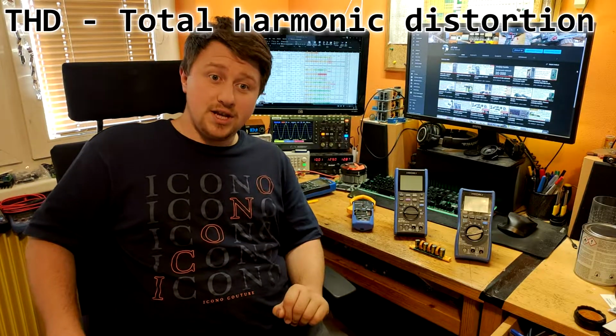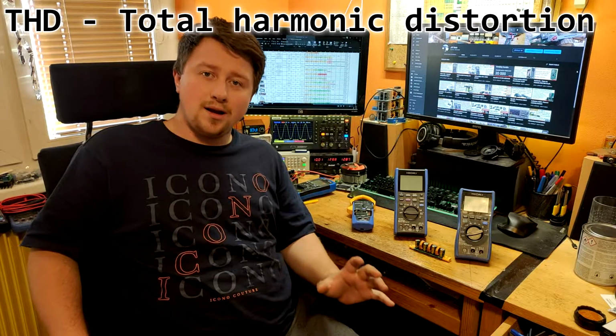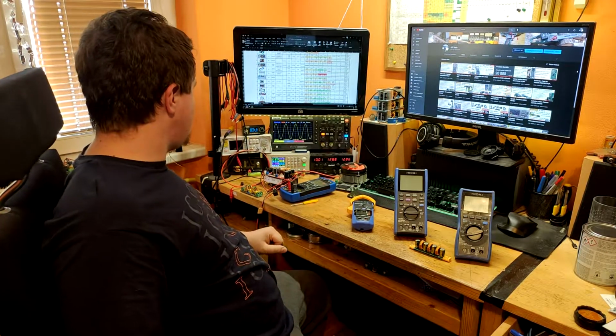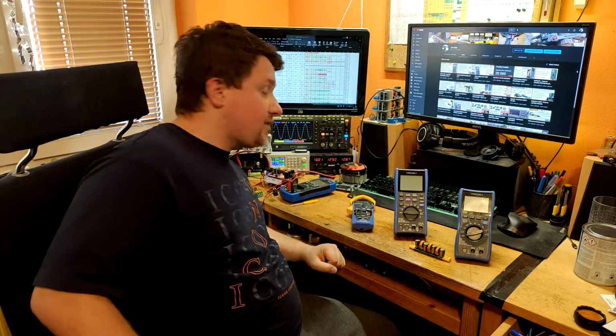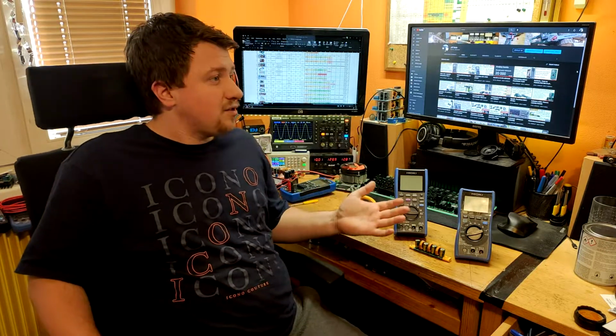Now, what is THD? THD tells you how ugly your sine wave is. THD is the sum of all your higher harmonics amplitudes divided by the amplitude of the fundamental first harmonic. In practice, we have switching mode power supplies, which are currently working at approximately 200 watts. We have variable frequency drives, or just almost every device, and their input current mostly isn't anywhere near sinusoidal.